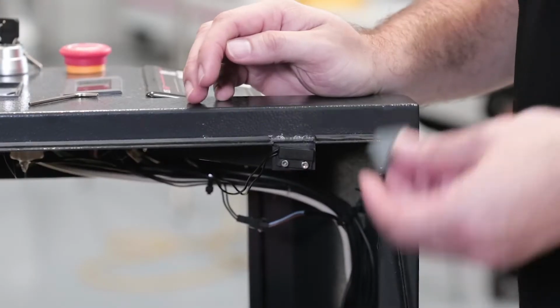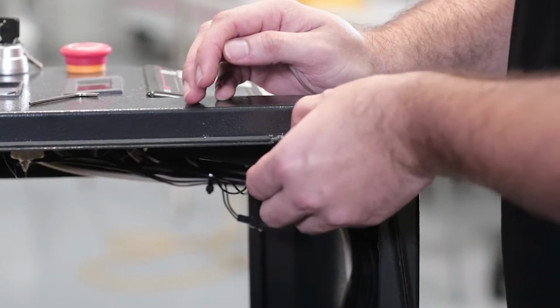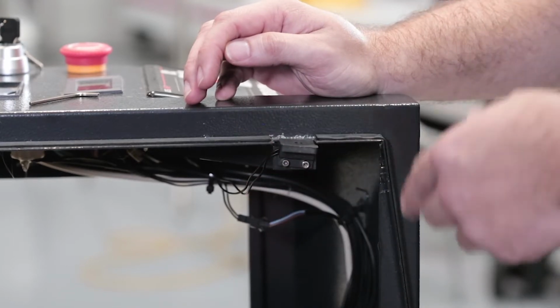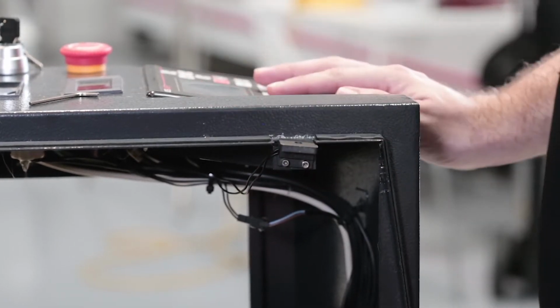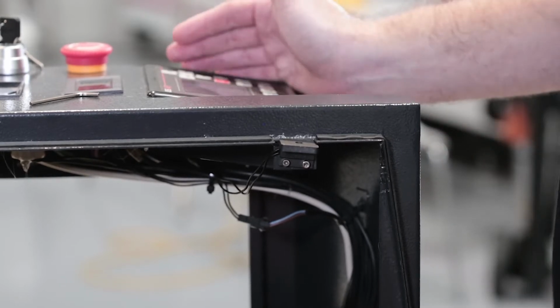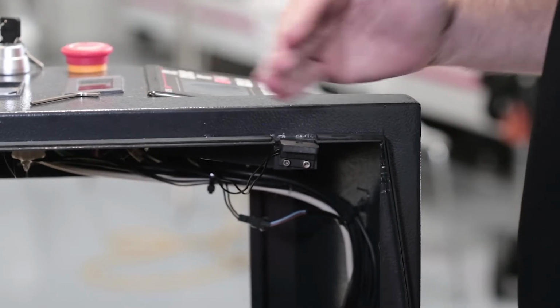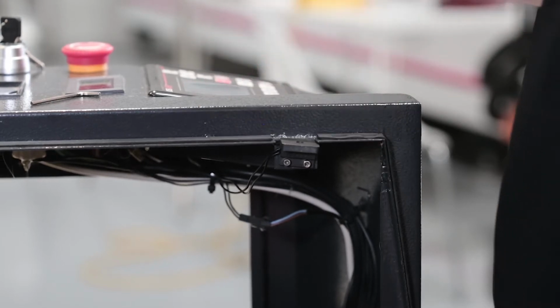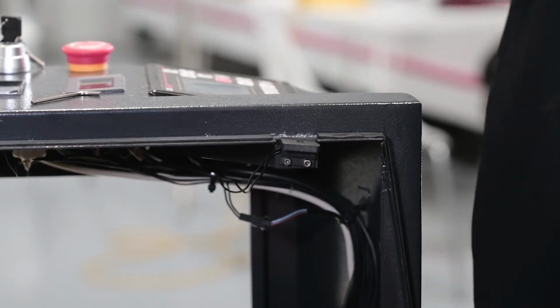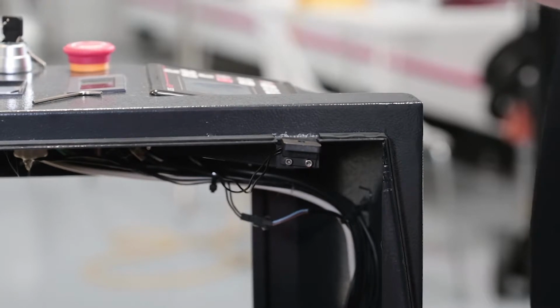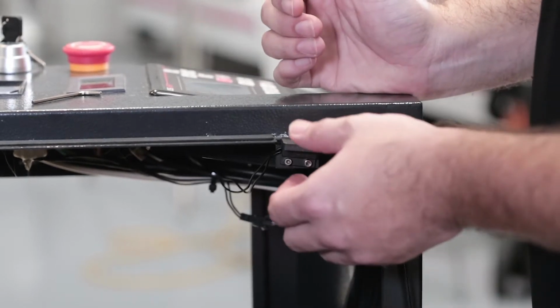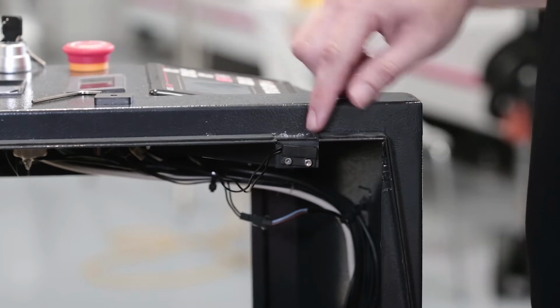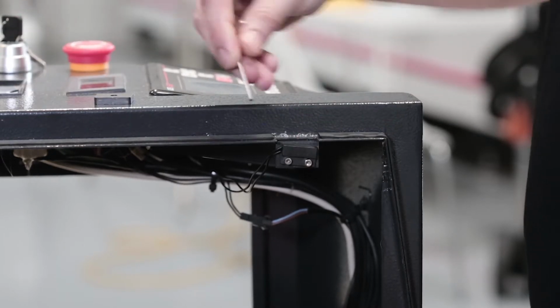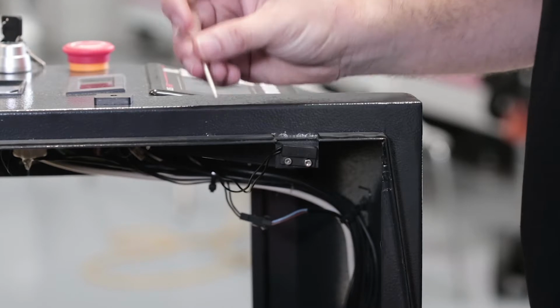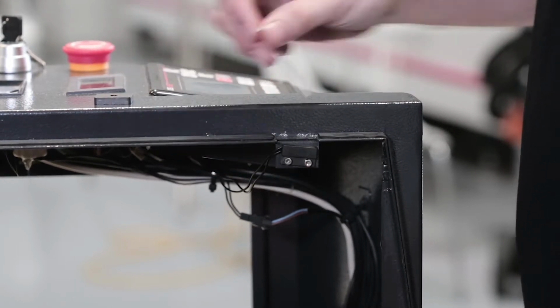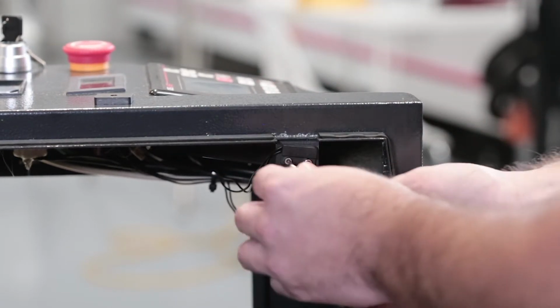Place your magnet on the door interlock. Once you do this, it will trigger the interlock. At this point, you can go ahead and press the pulse button on your control panel. If it fires, then that means that the magnet that's on the bottom of the lid on your hood is not making contact with the interlock. So at this point, we may need to just adjust your interlock. You're going to have 2 Allen screws here, and you're going to grab your Allen wrench from your toolbox and adjust it. And I'll show you how to adjust it here.